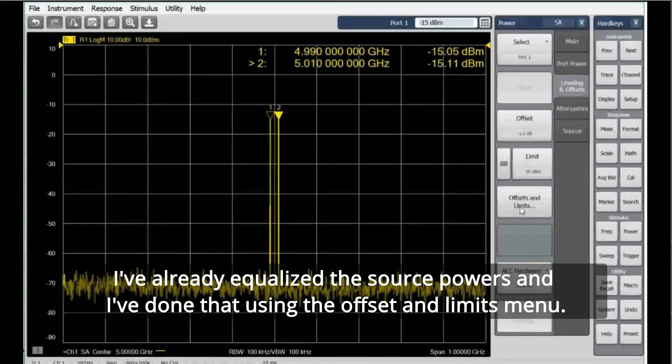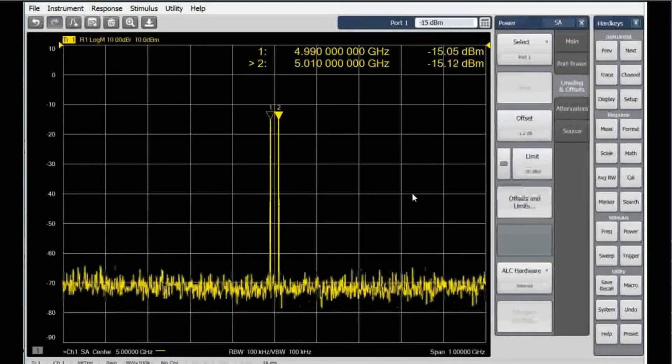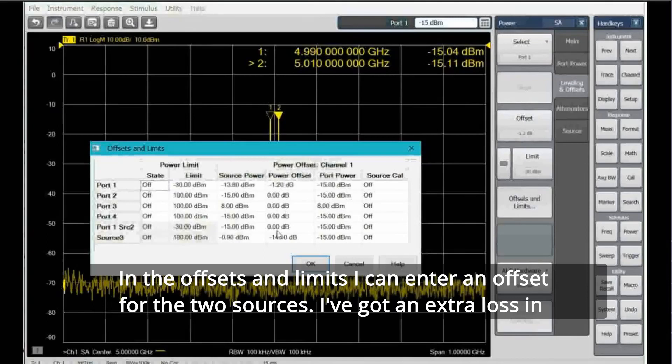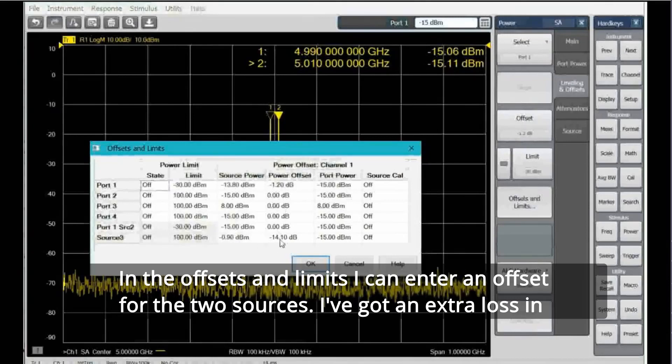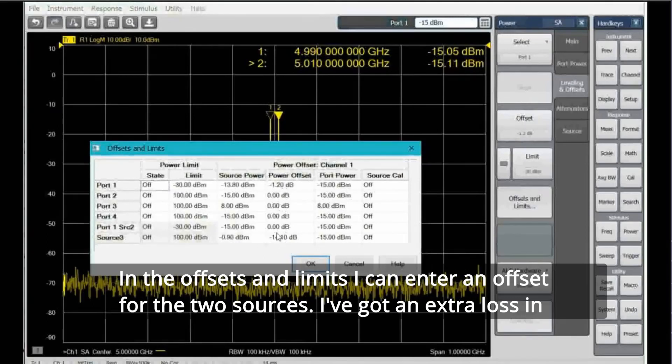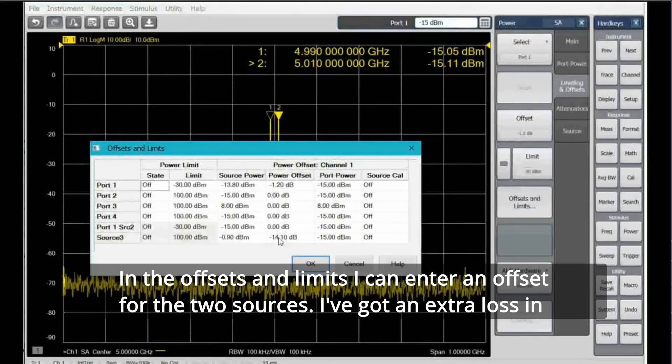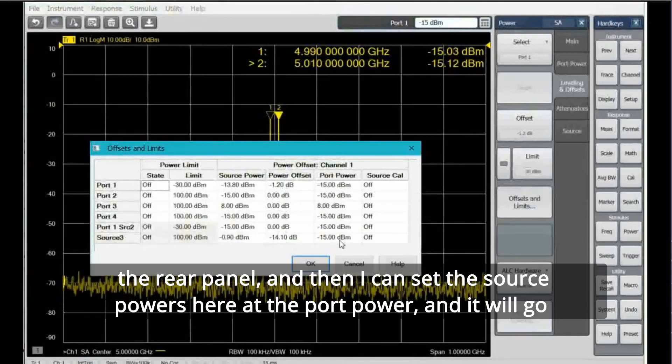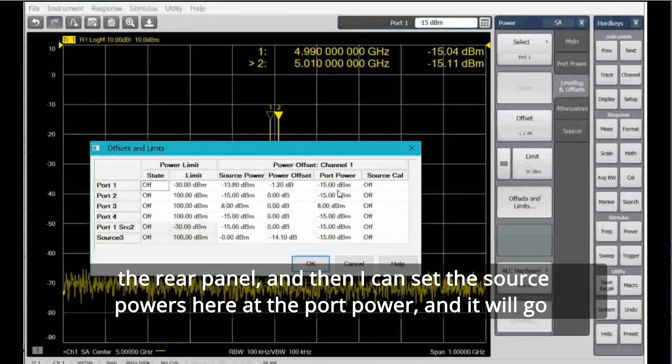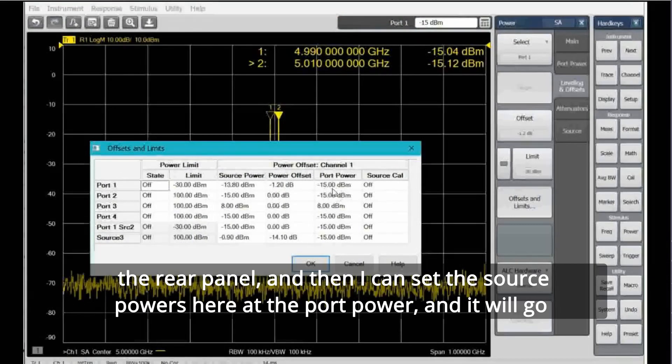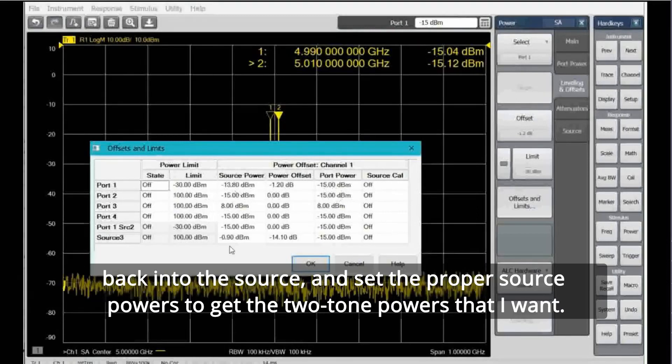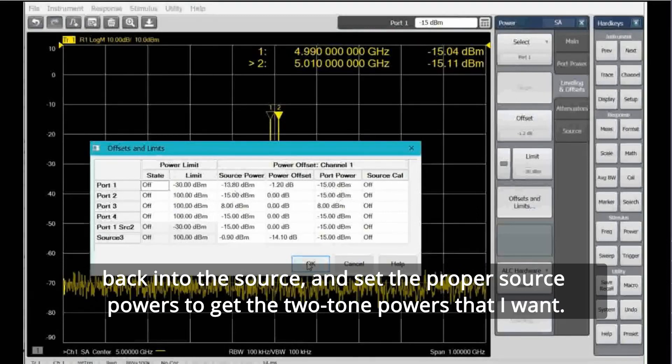I've already equalized the source powers, and I've done that using the offset and limits menu. In the offsets and limits, I can enter an offset for the two sources. I've got an extra loss in the rear panel, and then I can set the source powers here at the port power.